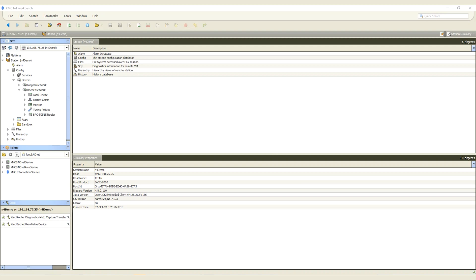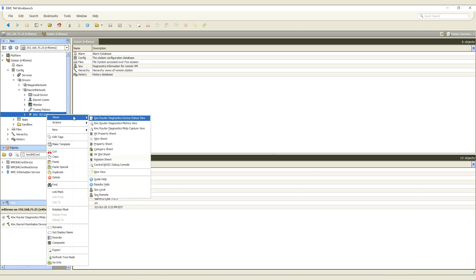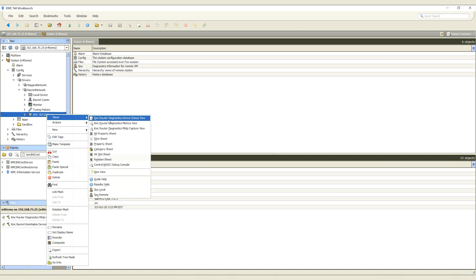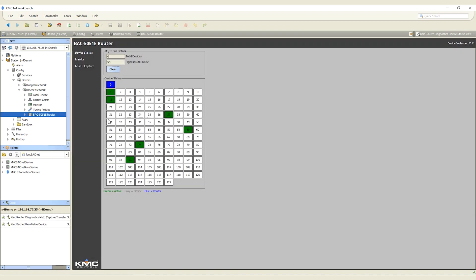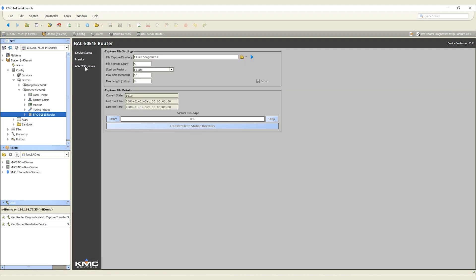KMC has added some of the router diagnostic features as part of the KMC BACnet module. To access the diagnostics, first you must add the router to your station as a KMC BACnet device. These features will be found as views on the BAC-5051E router once it's added to your station. Within these views, you can then access the device status, metrics, and MSTP capture, all from within the Niagara Workbench.